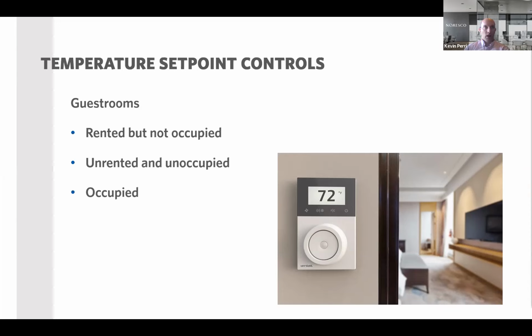And then you have a category of unrented and unoccupied, which to me is basically just saying it's not being used. But anyway, they made that category, and that's saying that the temperature will be set back between 60 and 80. And then you have the occupied set point, which, anybody want to take a guess on what that means? It's pretty straightforward, right? Somebody's in the space, and when they're in the space, it's going to be running at the occupied set points.